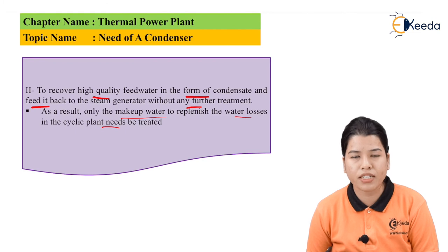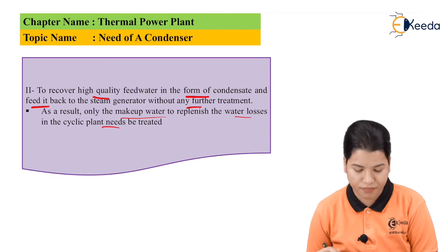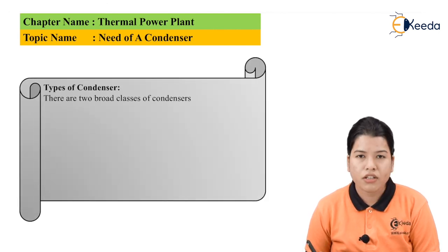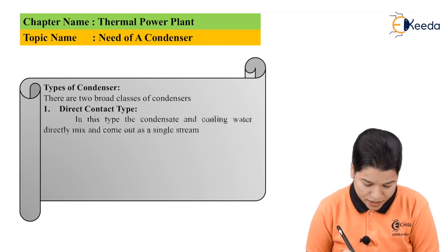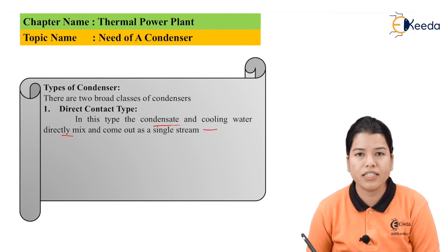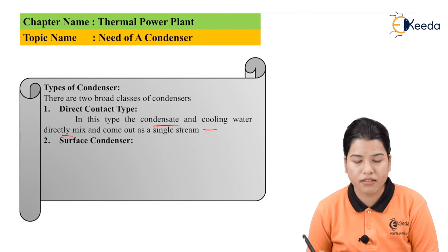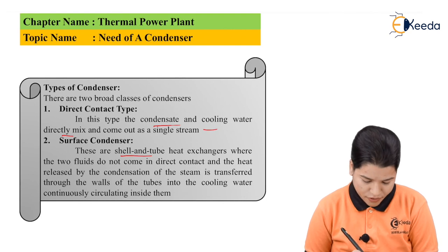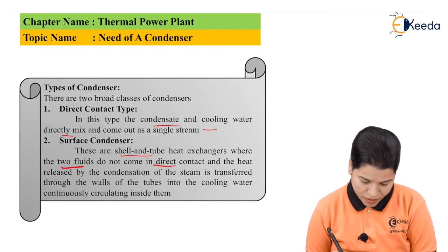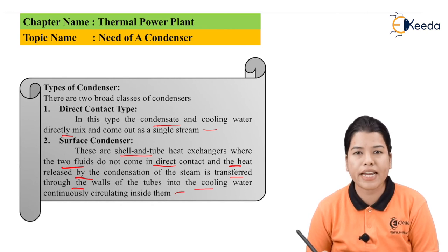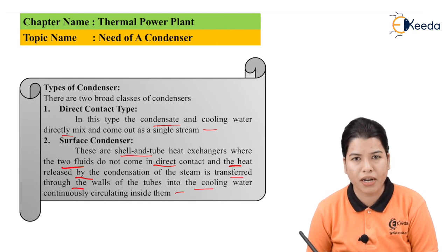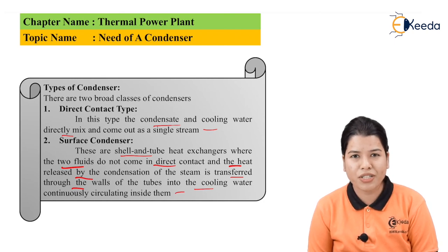These are the two reasons due to which condensers are used in the thermal power plant. Condensers are classified into two broad types. The first is the direct contact type, where the condensate and the cooling water are directly mixed and come out as a single stream. The second is the surface condenser, which is a shell and tube heat exchanger where two fluids do not come in direct contact; heat released by condensation of steam is transferred through the walls of the tubes into the cooling water circulating inside them. We will study these condensers in detail in upcoming videos. Thank you friends for watching this video, stay tuned with Ekeeda and do subscribe to our channel.